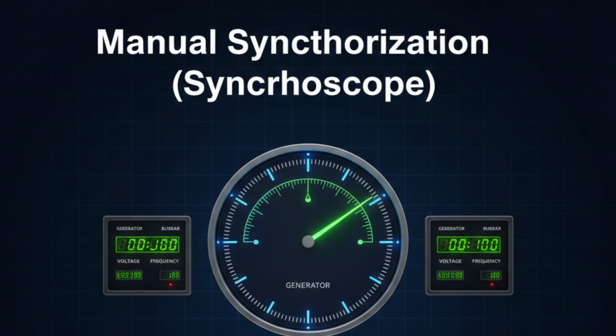Manual synchronization, synchroscope. Now let us understand manual synchronization using a synchroscope. A synchroscope shows the phase difference between the busbar and the incoming generator. The needle rotates clockwise or anti-clockwise depending on frequency difference. If it rotates clockwise, incoming frequency is higher. If anti-clockwise, frequency is lower. We adjust engine speed using the governor control until the needle rotates very slowly. When the needle approaches the 12 o'clock position, that is the correct phase match. At that exact moment, we close the breaker. Timing is very important. If we close too early or too late, phase mismatch can cause heavy current surge. Manual synchronization requires skill, experience, and full attention. That is why many modern ships use automatic synchronization systems.